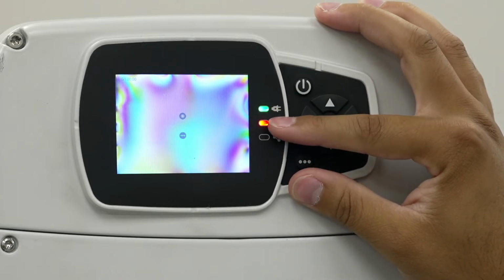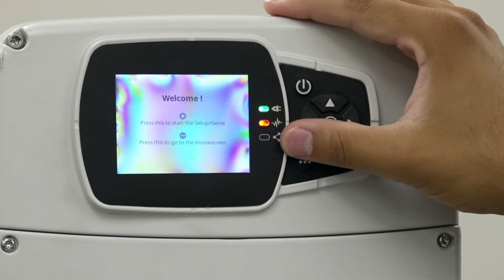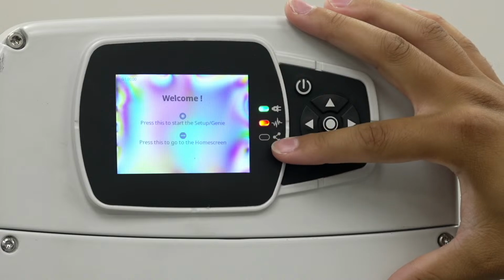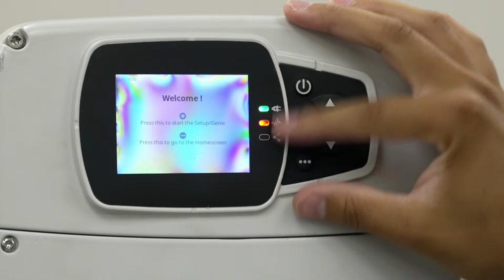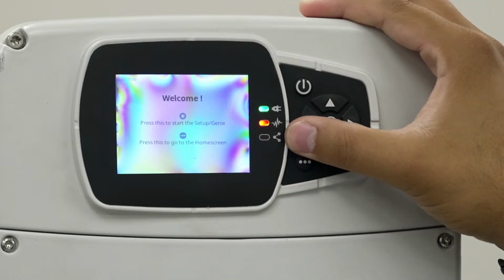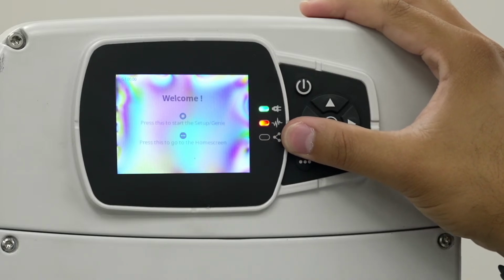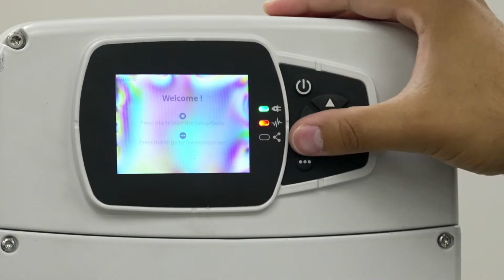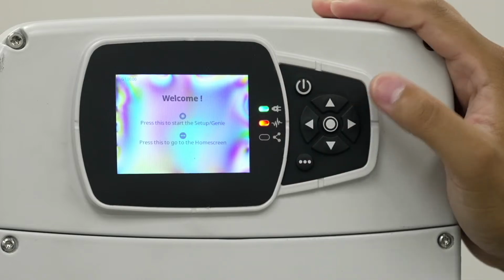So there could be a case where this is alternating between green and yellow, notifying that the motor is running, but there's still some sort of issue that you would want to look into. And then the last LED is your communication LED. So this will light up two different colors as well. It'll be green if you are communicating to a BMS or SCADA system. It'll be blue if you're connected via Bluetooth with your mobile application. And there could be times where you have both going. So that would alternate between blue and green if you are connected via Bluetooth and a BMS or SCADA system.